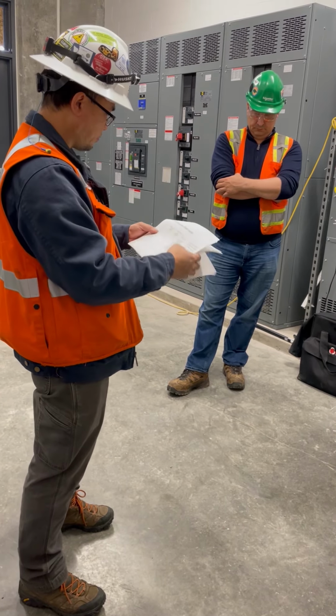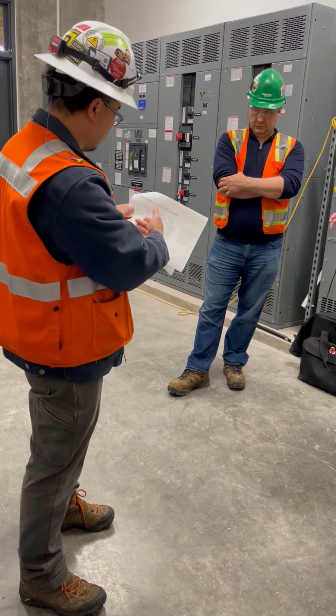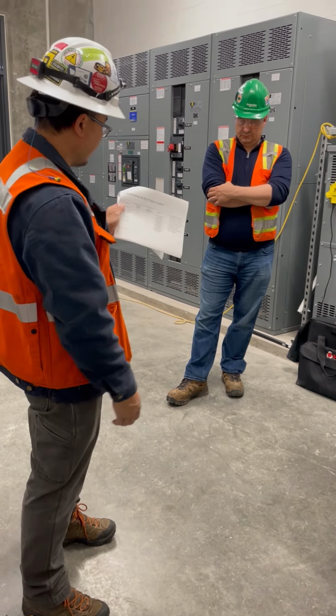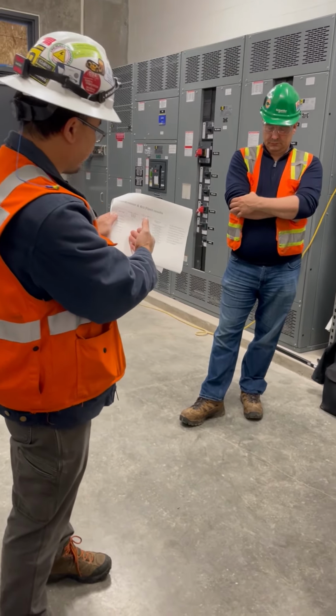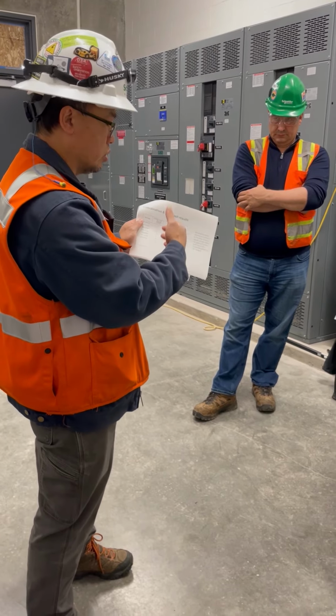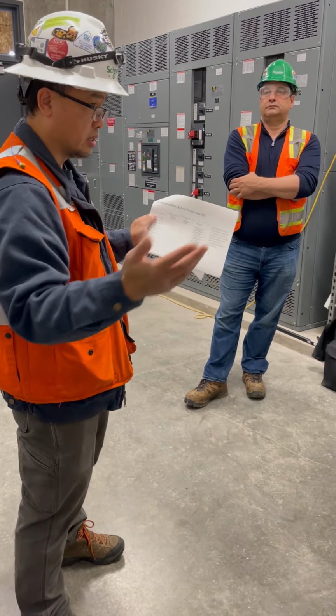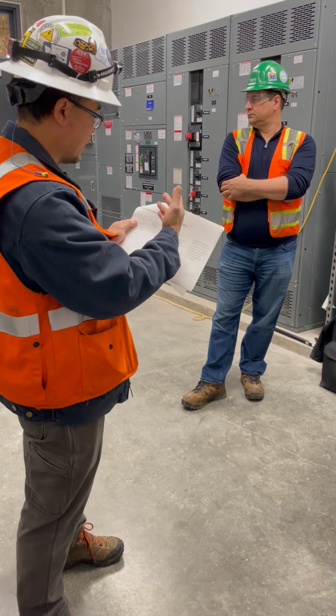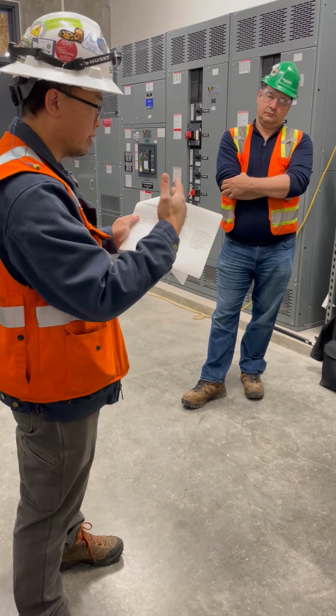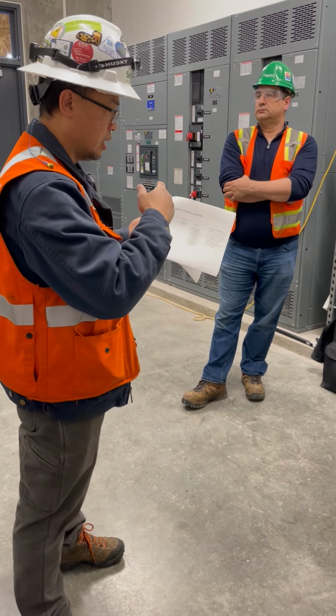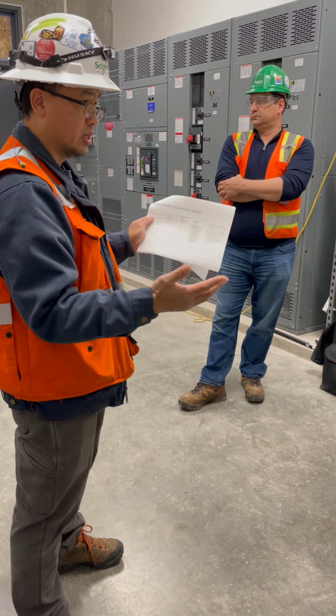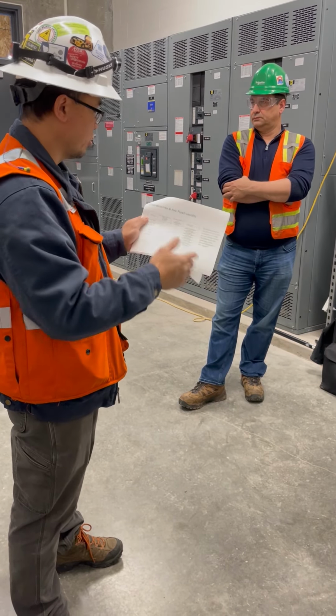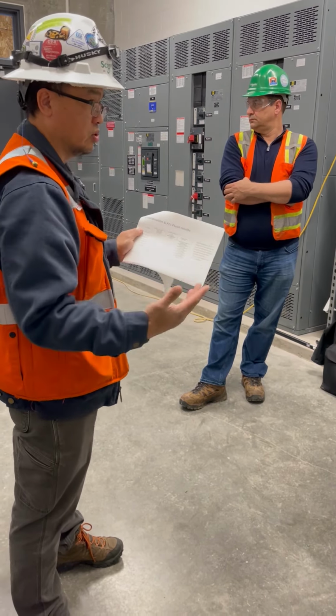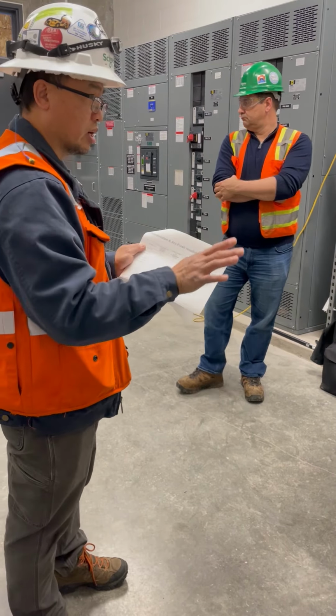Then, of course, this is as found and recommended. So we do studies for existing systems. We'll analyze existing systems and see what the available fault current and the arc flash incident energy are for the as found, and we can make recommendations. But for this, it's new construction, so we'll make the recommendations.